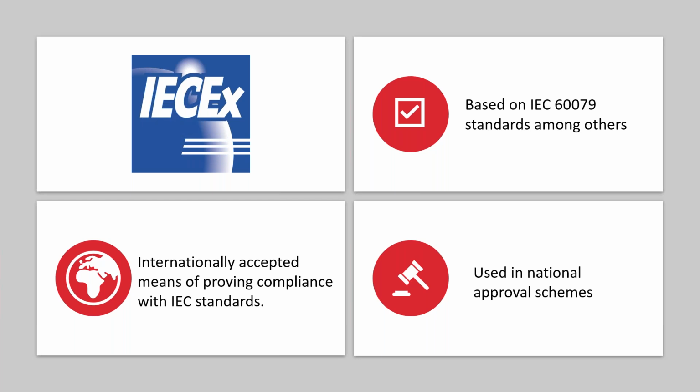However, under IECEx, it is also important to note that for manufacturers' products intended for use in potentially explosive atmospheres, manufacturers must be assessed by an ExCB, and a quality assessment report, or QAR, is issued and is required to ensure that the manufacturer is authorized to produce and sell certain types of IECEx equipment. So that's the international scheme.